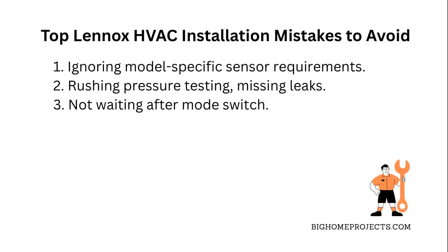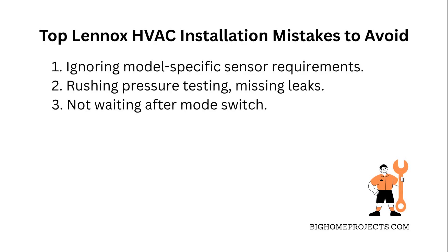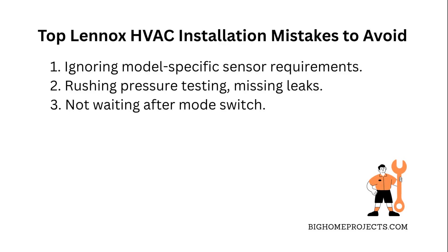Fix it by confirming if your furnace model has built-in sensor terminals — if yes, nix the external board. Another common issue is rushing through pressure testing without confirming there are zero leaks, which can cause false alarms and system errors. Take your time and double-check for leaks thoroughly.